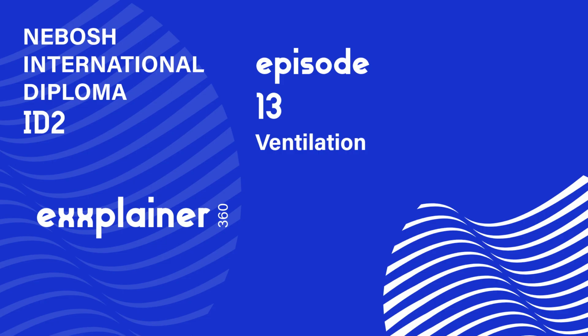You mentioned something surprising about cyclones earlier. Yes. Here's the thing with cyclones. Because they spin the air and particles so vigorously, friction can actually generate static electricity. Really? Static? Yes. And if the dust you're collecting is combustible, like wood dust, flour, some metal dusts, that static spark could be the ignition source for a dust explosion inside the cyclone. Wow. So the safety device itself introduces a pretty major explosion hazard.